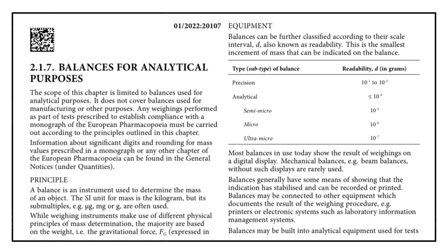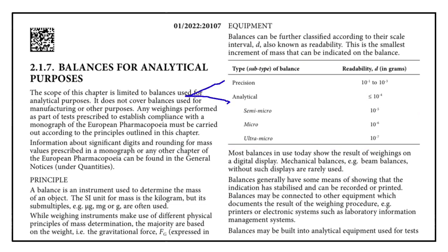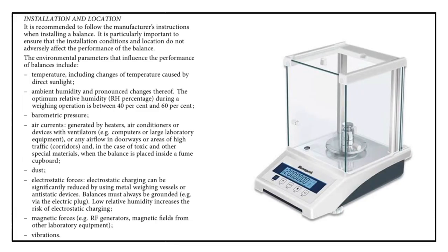EP chapter 2.1.7 classifies analytical balances into two major types: precision balances and analytical balances. Analytical balances are further classified into three types: semi-micro balances, micro balances, and ultra-micro balances. A separate video on the types of balances is available in the description for more details.